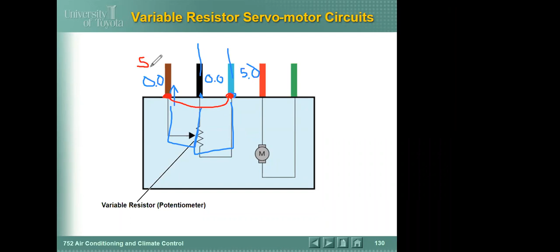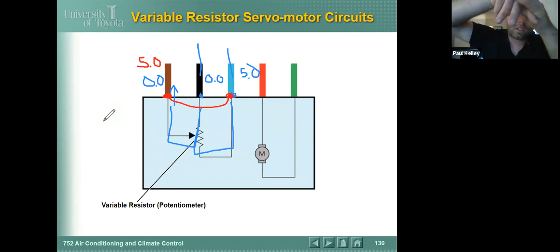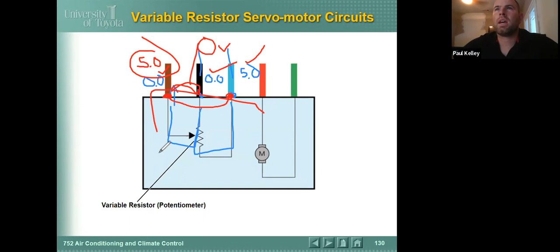If you don't want to get your meter and test all sorts of stuff, a lot of times you can look at the actual voltage on the text stream. If you can find the voltage or the reading on the text stream, you could disconnect the sensor. You can jump the 5 volts to the signal and it should peg it one way. Then undo your jumper and jump the ground to the signal and it should peg it the other way. So if I jump 5 volts to signal and it reads 5 volts, cool. And if I jump ground to signal and it reads 0 volts, that tells me this is good, this is good, this is good. All these wires are good. That tells me the actuator's bad.